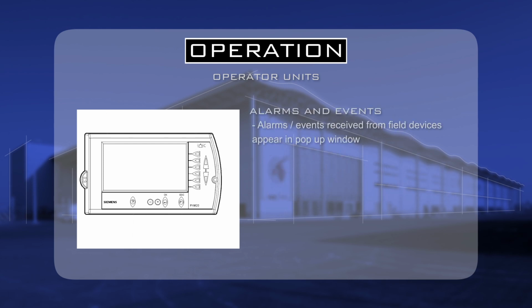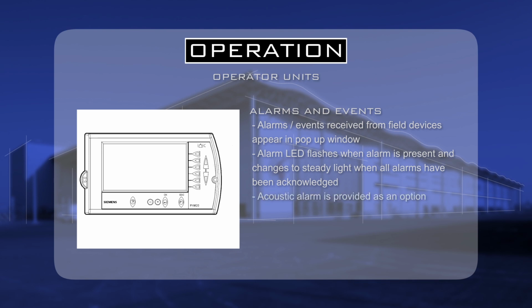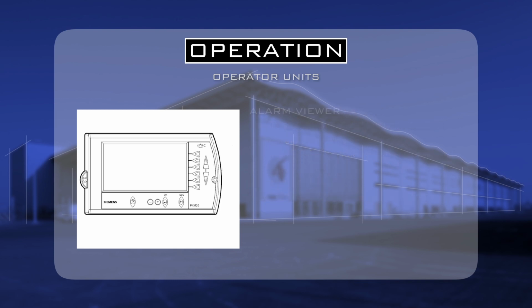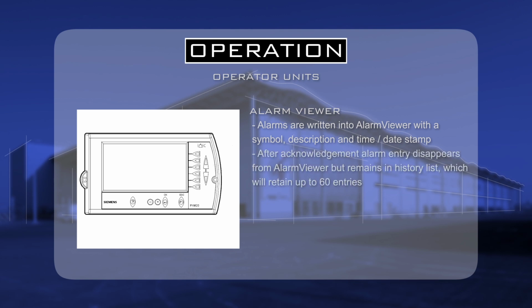Alarms and events received from field devices appear in the pop-up window. The alarm LED flashes when the alarm is present and changes to a steady light when all alarms have been acknowledged. An acoustic alarm is provided as an option. Alarms are written into the alarm viewer with a symbol, description, and time and date stamp. After acknowledgement, the alarm entry disappears from the alarm viewer, but remains in the history list, which will retain up to 60 entries.